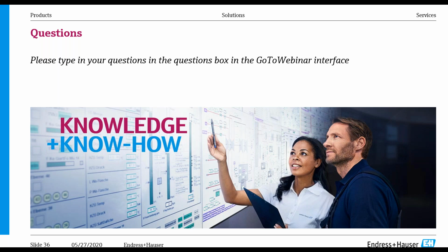Thanks, Jason. I've got another question for you from Khaled. He asks, what are the upstream or downstream meter run requirements, if any? Okay, it depends on what accuracy you want to obtain. I always said we had two different accuracy statements. For standard volume flow, not corrected, it was 0.5% and 1%. If you want to get to that 0.5%, you're going to need 20 pipe diameters. If you want 1% only, then it's 10 pipe diameters upstream.